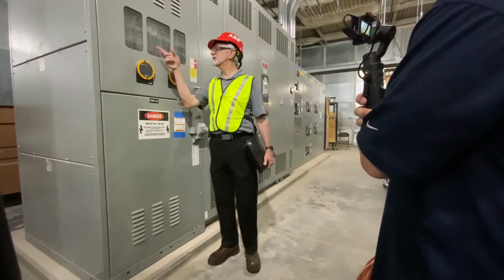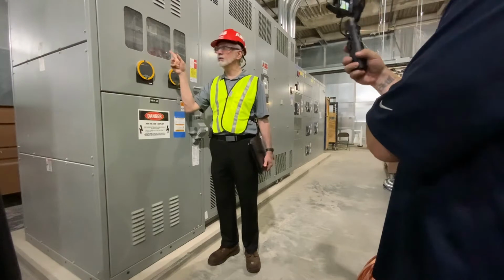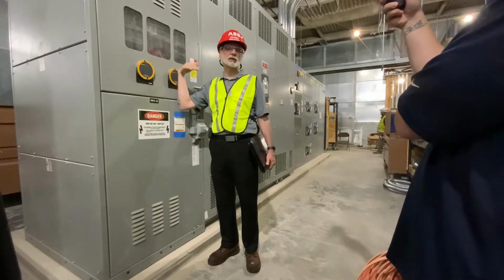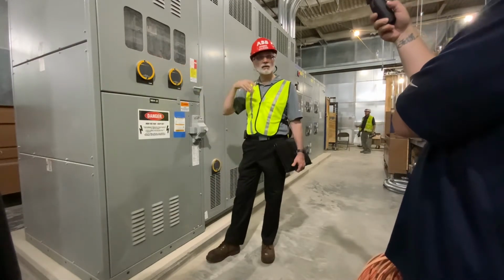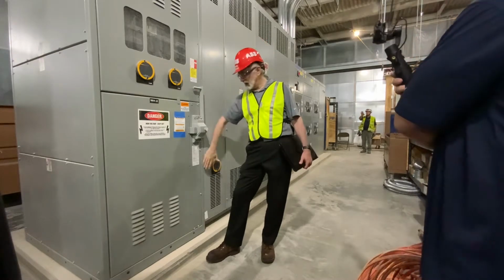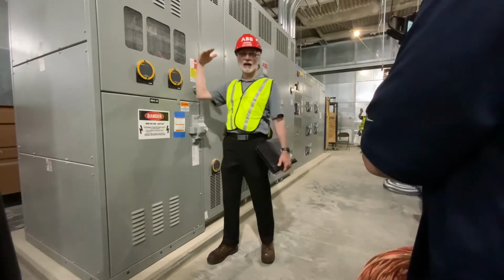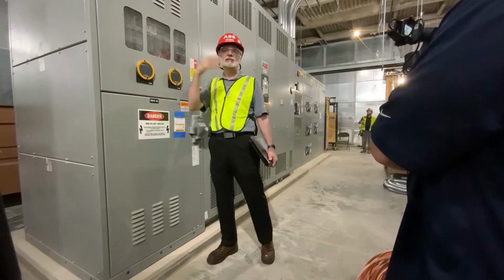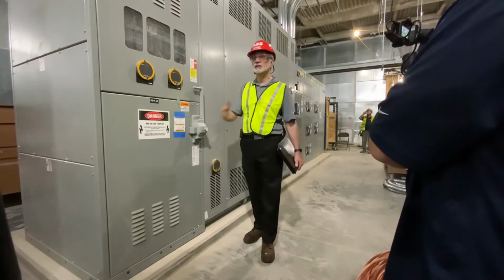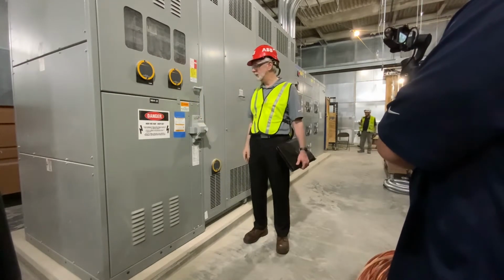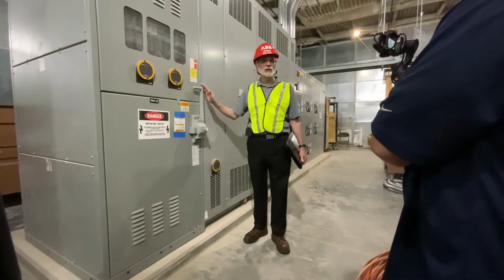The nice thing about this is you'll get positive viewing through the window if the blades are in the open or disconnect position. So, another nice double check. Hey, the switch tells me it's open. Can I visibly see the blades? That would be the two-step process for safety, just to make sure before you open up the door. Any questions on the load interrupter switch?